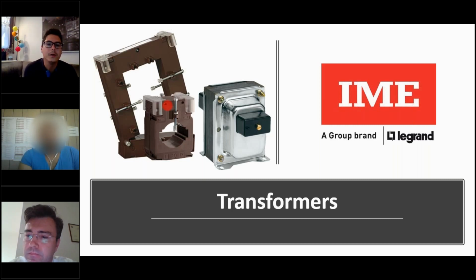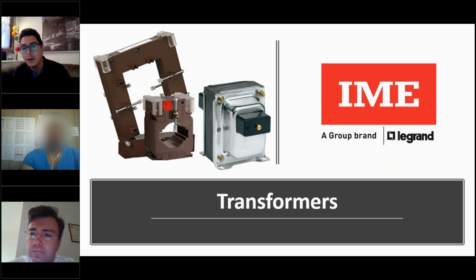If you only need to keep the current under control with an analogic instrument, you can go with a class 3 current transformer. But with these high values of power, surely you find a class 1 or class 0.5 current transformer, depending on the performance, depending on what you connect on the secondary of the current transformer.